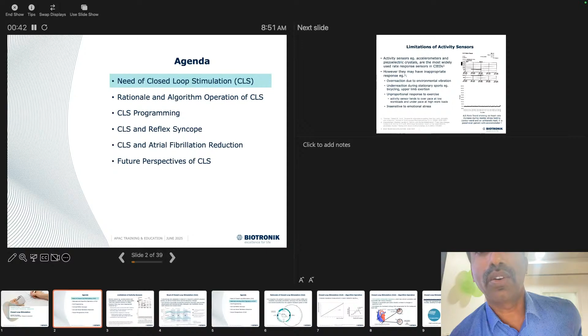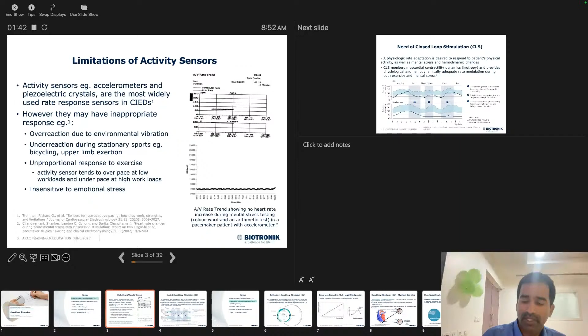To start off, we all know that there are a lot of sensors available. Very few are used, like the accelerometer, piezoelectric, and dual sensors from Boston Scientific. The major sensor used in all pacemakers is the accelerometer, and it's an open loop sensor. That means whatever the physician or technician programs, the rate, gain, threshold, all these inputs to the device, are taken over by the device. Whenever there is patient activity, the accelerometer gets activated and the rate is increased. So this is an open loop sensor, which doesn't have any feedback from physical activity or mental stress.